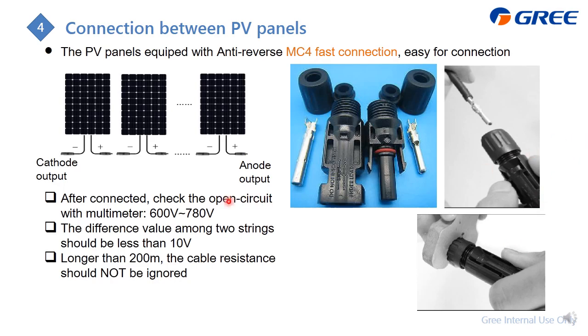And after they are connected, you need to check the open circuit voltage with the multimeter. It should be within this range. If there are multiple strings, the voltage difference between these strings should be less than 10 volts. And if the cable length is more than 200 meters, you need to consider the cable resistance.